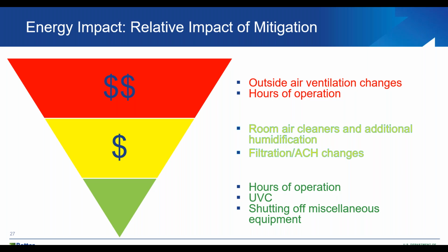The next one is changes made to room air cleaners, additional humidification, filtration, even additional air change per hour rates. If they're not significantly increased, you will be using more energy, but it may be a way to go in terms of how to run under COVID-19. And then there are some other means, your hours of operation. You may actually be shutting off equipment or shutting off HVAC, not providing heating or cooling if you have spaces in your building that are not currently in use right now, and there's no reason to heat, cool them, or provide outside air to them. And UVC is also one. I've done a few calculations. It's probably you save a little energy from it. You have additional energy from the lighting, but you have other benefits from it as well. So actually you could use a little less energy as a result of it. Next slide, please.